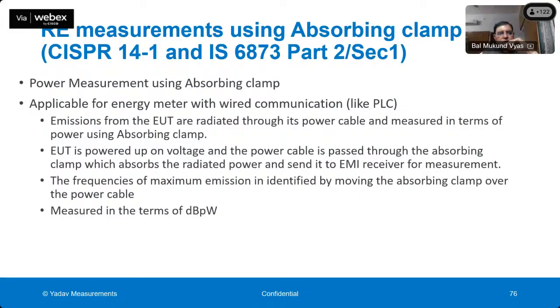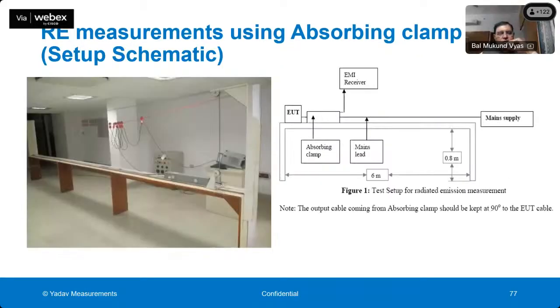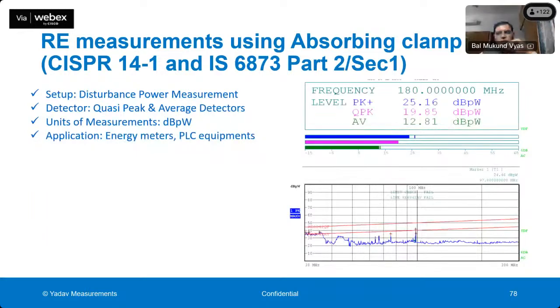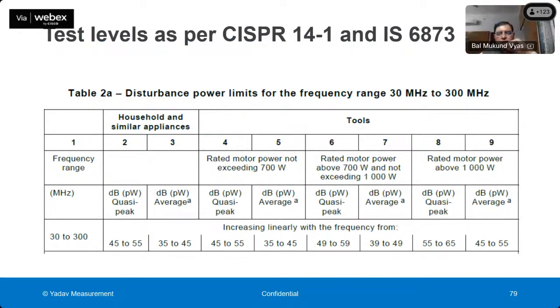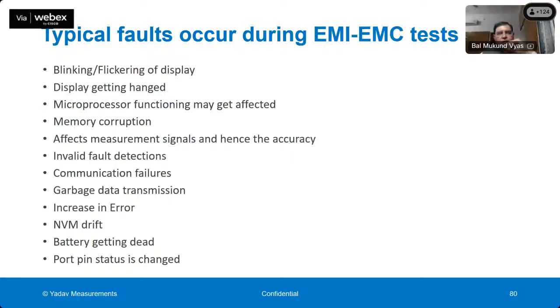A similar kind of test can be done using the absorbing clamp as per CISPR 14-1 or IS 6873. So this kind of arrangement is used for measuring the radiated emission from the meter. This also specifies the radiated power as per IS 6873. Similar limits are specified.